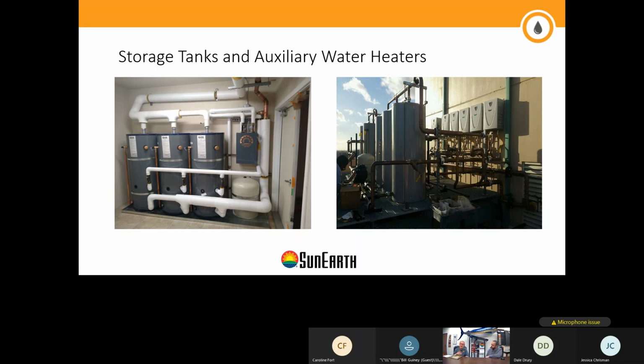When you're retrofitting, for example, if this was upstairs on a third story, hopefully the floor that it's on, the room it's in, is rated to handle the weight. And in retrofit, you've got a lot of things to think about. Leakage, is the room sealed for water? Is there a drain? Is there adequate drainage? You can see here they use this big pan to basically make sure to catch any leaks.